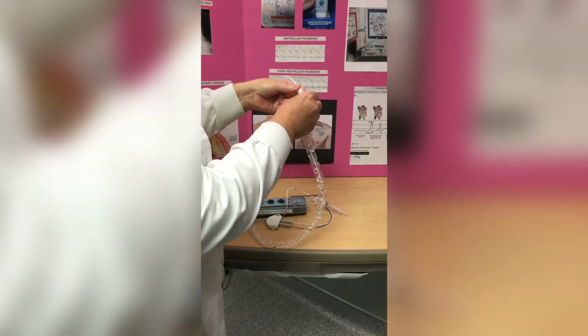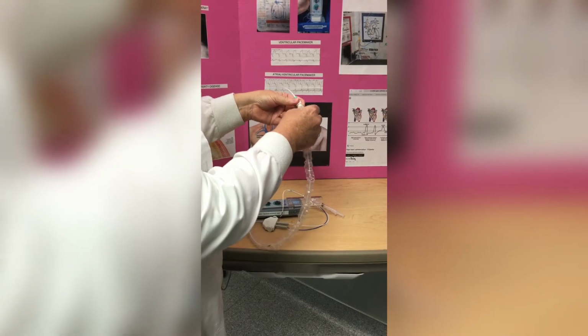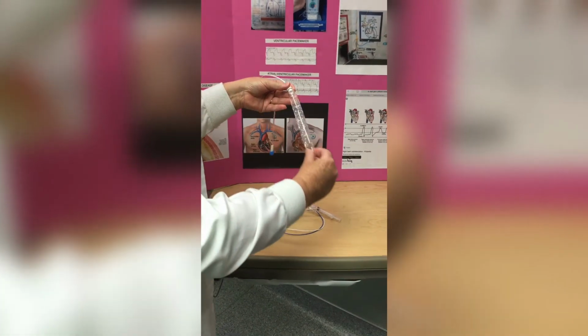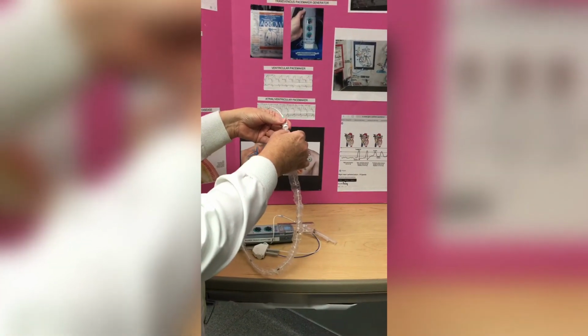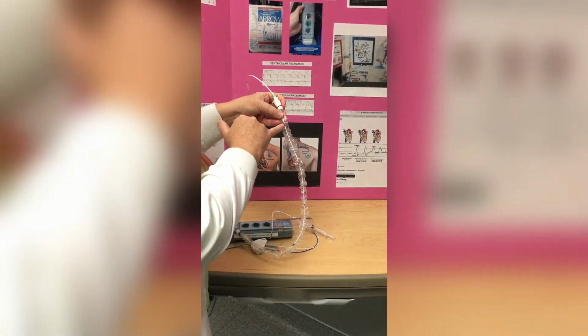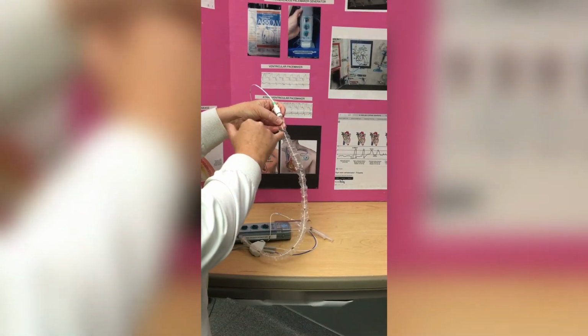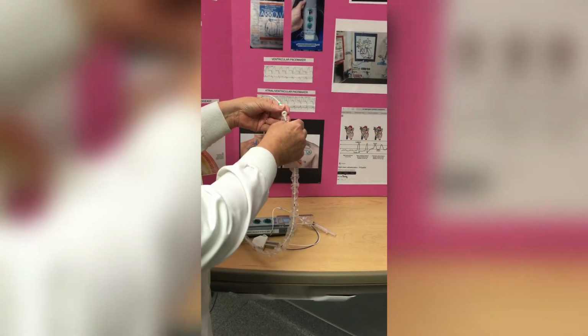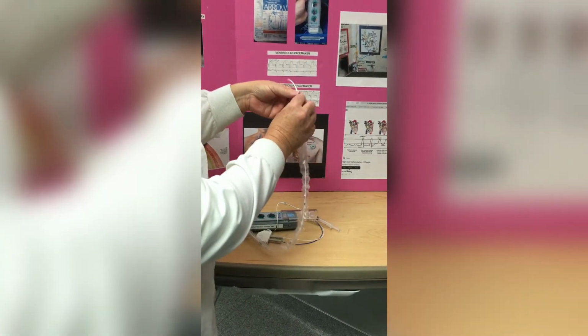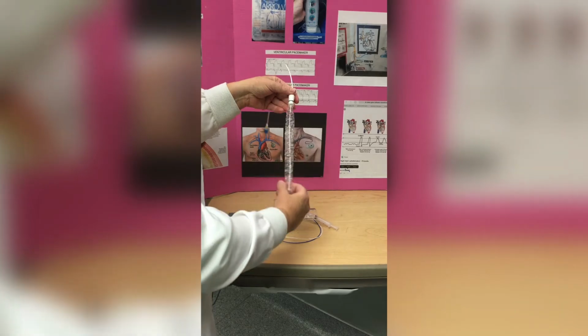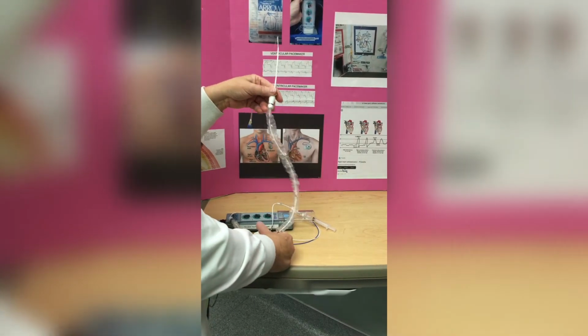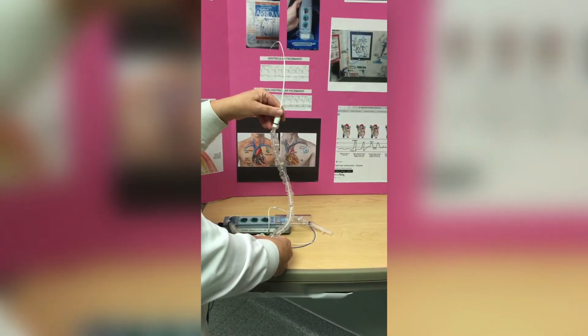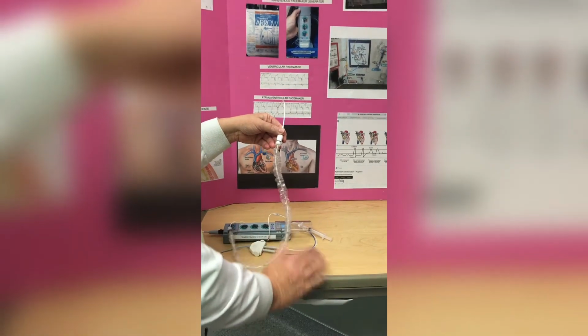He could still move it inside of the sheath if he needs to, but the problem is this thing does move. That's why you need to keep an eye on how many centimeters it's supposed to be, because there's not a true locking system on this sheath here. It locks onto here, but it still has the possibility of moving. That's why documentation is so important for the placement of a pacemaker.